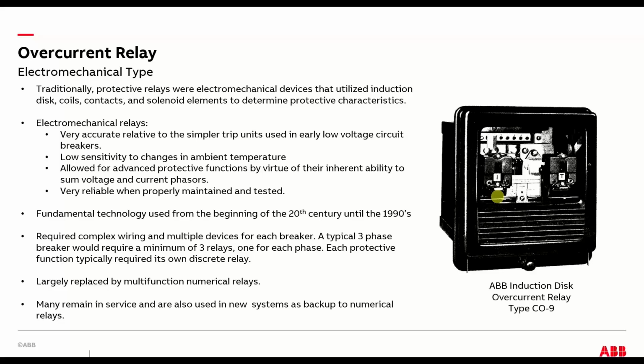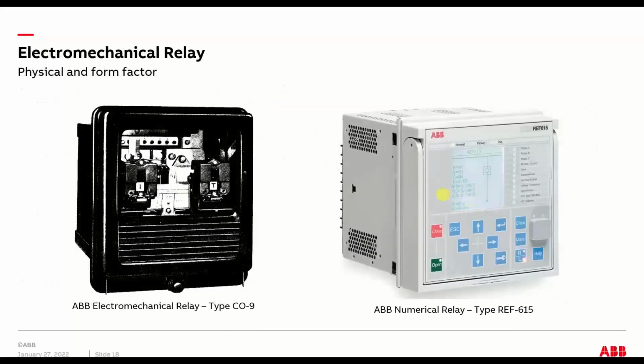Now that's all changed, and in my mind, there's no real difference in the accuracy you can get between a low voltage circuit breaker with an electronic trip unit and a high-end relay. They started out in two different directions for two different applications, but now they very much overlap in what you can do with them. But this last point's kind of good. I know a lot of these are still in service, so I expect some of you are going to get applications where you put a new system on and utilize multifunction relays, but you have to coordinate it with an old induction disk. So hopefully this will help you out, because these have been around for a long time and they're not going anywhere.